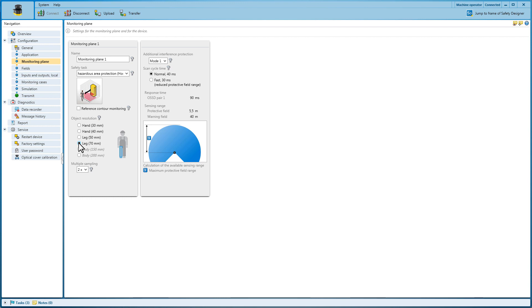The object resolution has an influence on the maximum protective field range. If necessary, multiple sampling — meaning how often the scanner has to detect an object before it is perceived as such — can be changed. The multiple sampling rate influences the response time of the OSSDs.